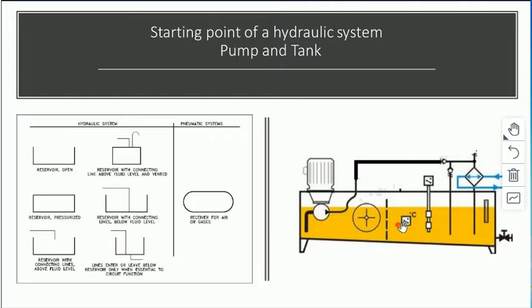Then the tank needs to have a level indicator, and temperature indication as well. You can see the level indicator here, follow the cursor, and then you can see the temperature gauge here. Pressure should be pretty much zero, it should be depressurized once it ends up in the tank. And then the pump picks up the oil and generates a pressure. When we look at this little diagram here, all it is telling us is that everything goes back into the pump, and then here we've got a bit of valve operation, but everything goes back into the tank.